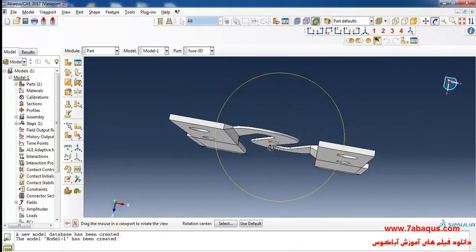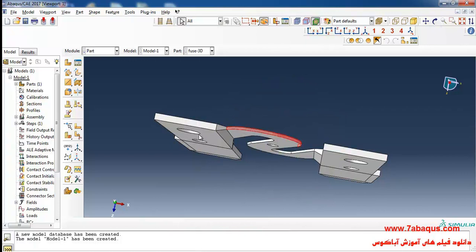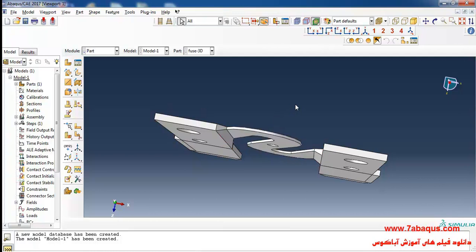The thickness of the fuse element is by far lower than the thickness of the blades. The reason for this is that if the current passing through the fuse exceeds the allowable level, the middle section — which has less thickness — might start melting and the current would come to a halt. Since the middle section has less thickness, it would melt sooner.